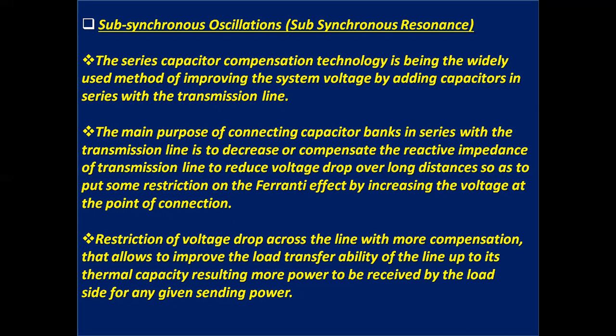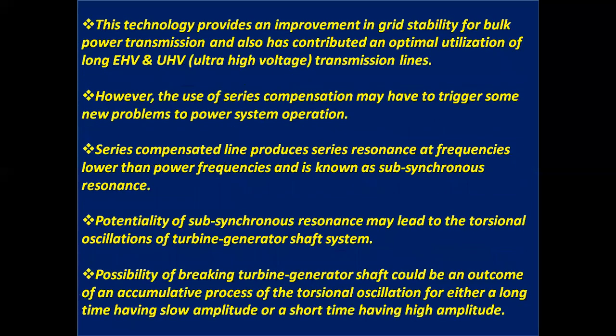Number 3, restriction of voltage drop across the line with more compensation allows improving the load transfer ability of the line up to its thermal capacity, resulting in more power being received by the load side for any given sending power. This technology provides an improvement in grid stability for bulk power transmission and also contributes to optimal utilization of long EHV and UHV, that is extra high voltage and ultra high voltage, transmission lines.